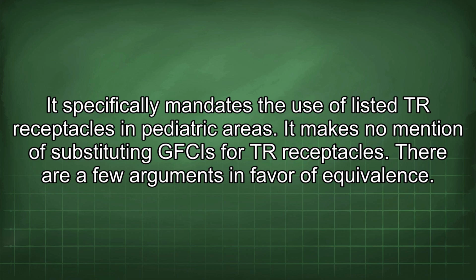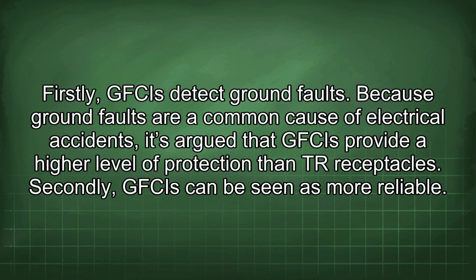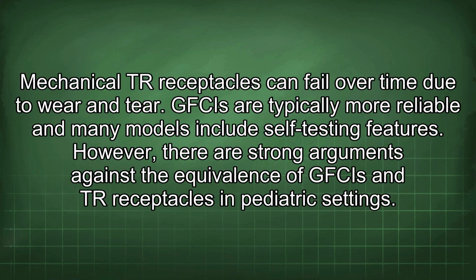There are a few arguments in favor of equivalence. Firstly, GFCIs detect ground faults. Because ground faults are a common cause of electrical accidents, it's argued that GFCIs provide a higher level of protection than TR receptacles. Secondly, GFCIs can be seen as more reliable. Mechanical TR receptacles can fail over time due to wear and tear. GFCIs are typically more reliable, and many models include self-testing features.